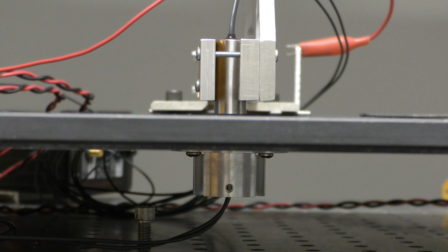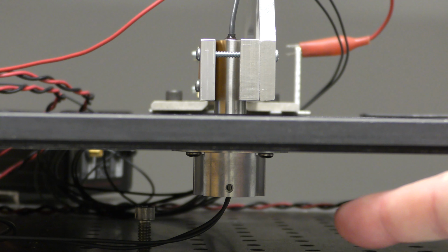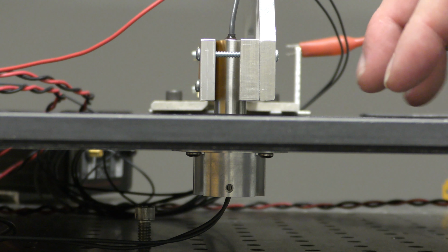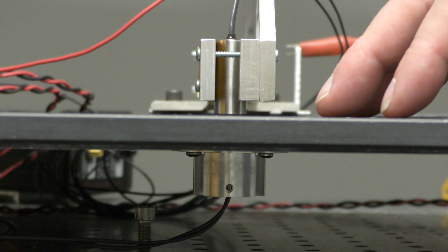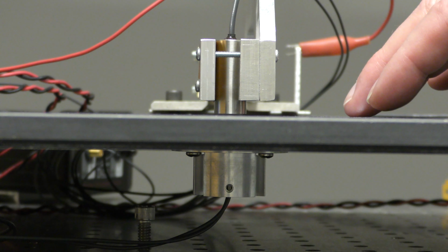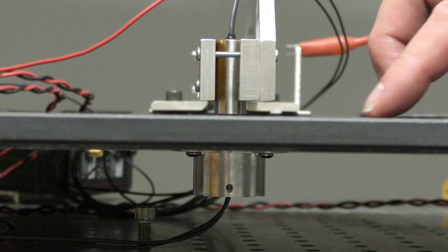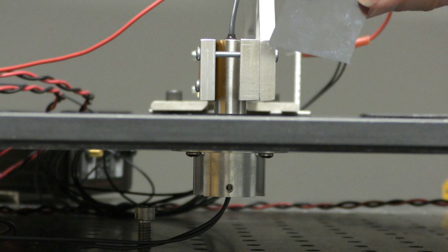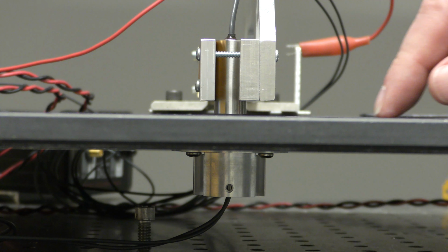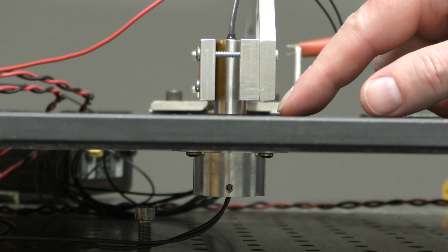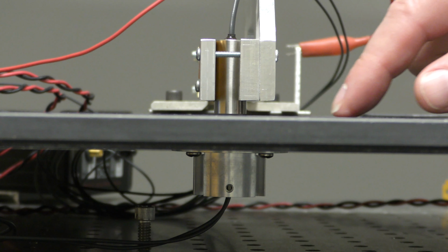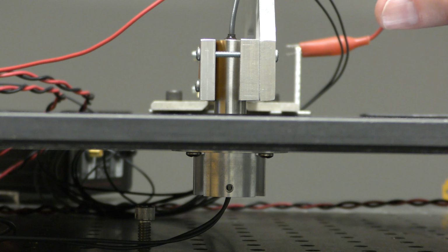In our setup here, we're looking at two probes, a top push-pull probe and a bottom push-pull probe. You can see down under here. And then we have a platen. This is an aluminum platen with a very smooth surface used to put silicon wafers on. Here we have a sample of a silicon wafer, so we can slide target material underneath the probes. And we're doing a full differential measurement to measure the thickness.